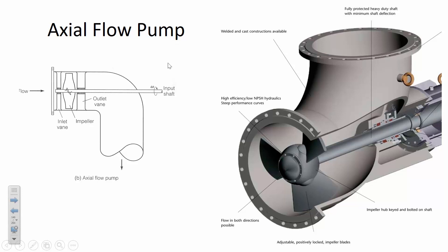An axial flow pump adds energy the same way — an impeller accelerates the fluid, adding pressure — but it allows a really long drive shaft mounted at the surface. The impeller can be submerged hundreds of feet underground in an aquifer while the motor stays at the surface where electricity and cooling are available. The key difference is that axial flow pumps don't change the direction of flow; the flow continues in the same direction on both suction and discharge sides.